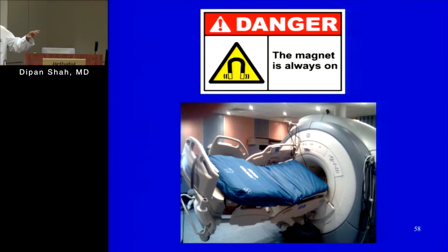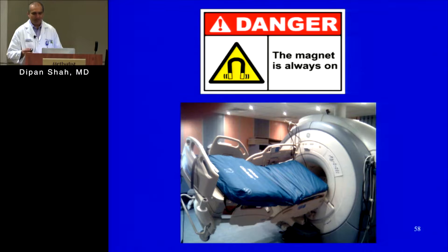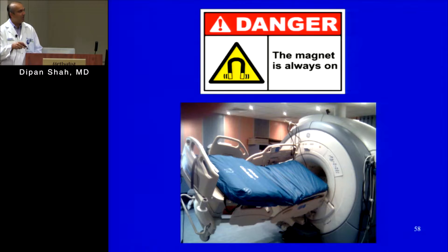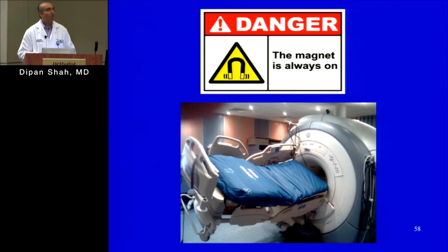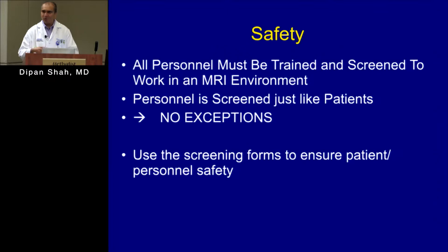Now we're talking about safety — this is critical. The magnet is ALWAYS on. If you forget that, you could get fired — or worse. This shows a case where someone wheeled in a bed with metallic components; it was attracted to the magnetic field, accelerated as it got closer, and became a projectile. There have been deaths — for example, a patient given an oxygen tank that flew and struck them. Safety is paramount: the magnetic field is always present, even when no one is in the room.